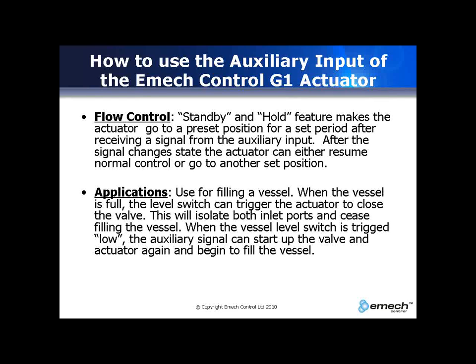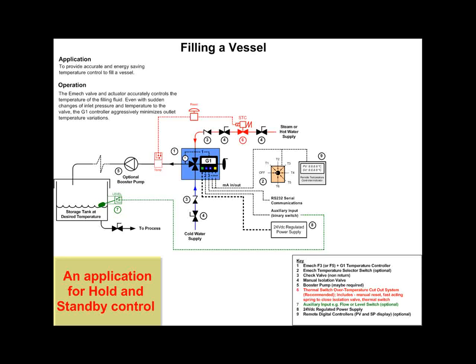When the standby and hold features of the actuator are enabled, the actuator will go to a preset position for a set period of time after receiving an enable signal from the auxiliary input. After the signal changes state, the actuator can either resume normal control or go to another set position. A typical application would be filling fluid in a vessel. The actuator will accept an enable signal from the vessel level switch. When the vessel is full, the level switch will trigger the actuator to close the valve. This will isolate both inlet ports of the valve and cease filling the tank.